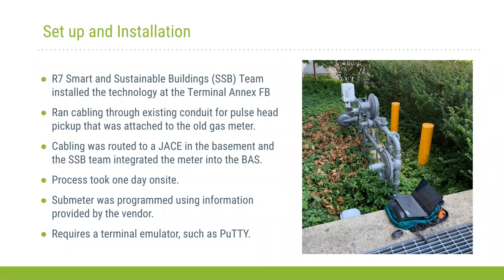Kevin pointed us in this direction to help support a different GPG project. We got Cat 6 cable, used the existing conduit line, ran the cabling into the building, and ran it to the closest Jace at this first site. In less than a day, really just a morning, we ran all the cabling, got the meter mounted on the wall, and connected it directly to the Jace. Then Bill Winger was gracious enough to do all the programming.